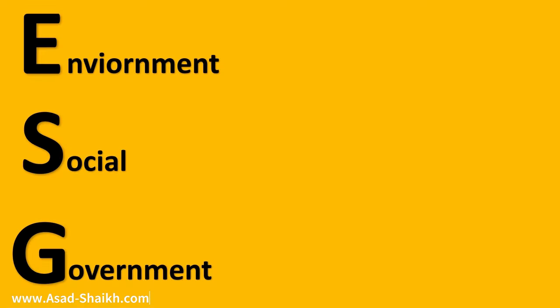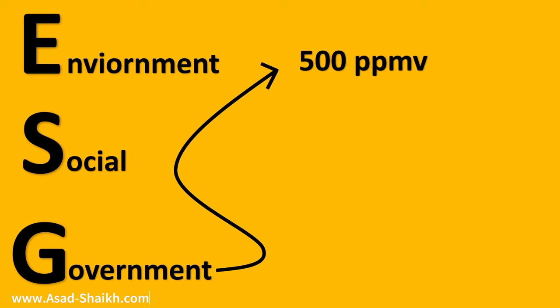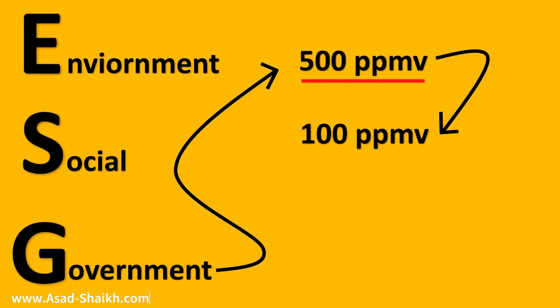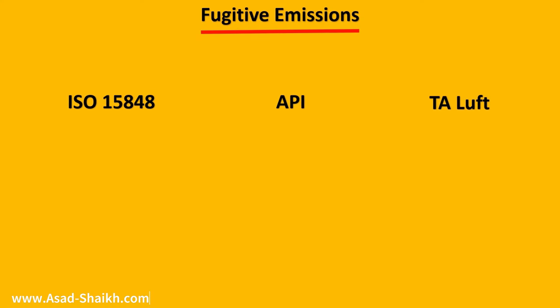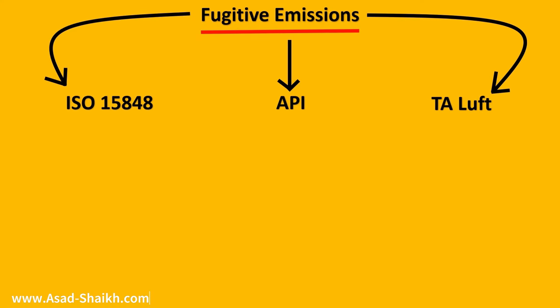You also have environmental, social, and government pressures coming in for industries. Government norms have become so strict that initially it used to be 500 parts per million in volume, then it became 100 ppmv, and now it is as stringent as 50 parts per million in volume, which is a very minuscule quantity. The fugitive emission standards used throughout the world are ISO 15848, API, and TA Luft standards in Germany.